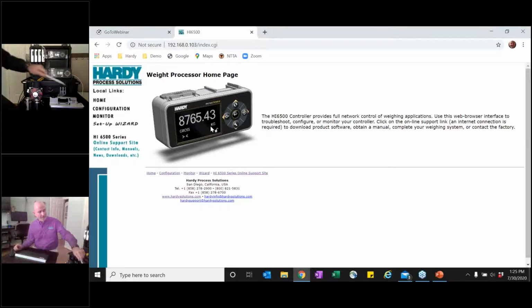I will say that both this unit and this unit are hooked up to the same load cell. This one has been set up so that it will always show you the correct weight. So you'll always be able to see the correct weight on this one. This one we're going to mess with a little bit. We're going to get it out of calibration, and then we'll perform a C2 calibration. Just to show you the equipment that we're using, this is a 1 pound certified test weight. We'll put it on here.